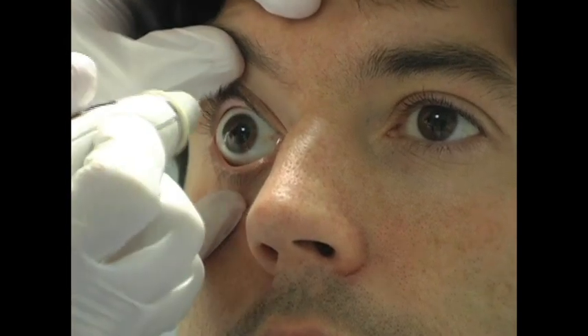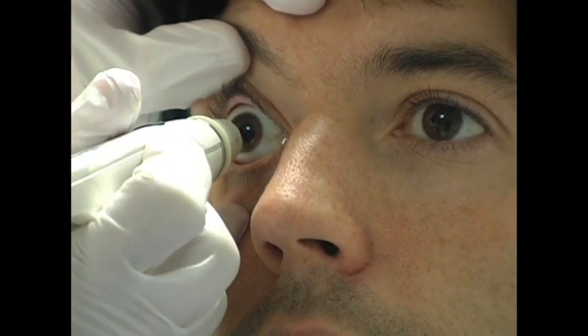If a patient's eyelids must be held open for testing due to involuntary squeezing or eyelid edema, make sure that you do not push on the eye itself, as this will falsely raise the IOP measurement. In these instances, try to hold the lid against the bony orbital rim to avoid putting pressure on the globe.